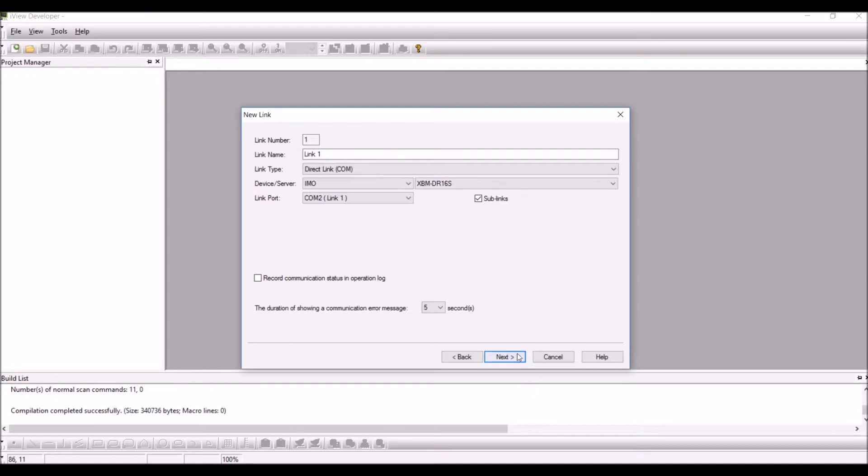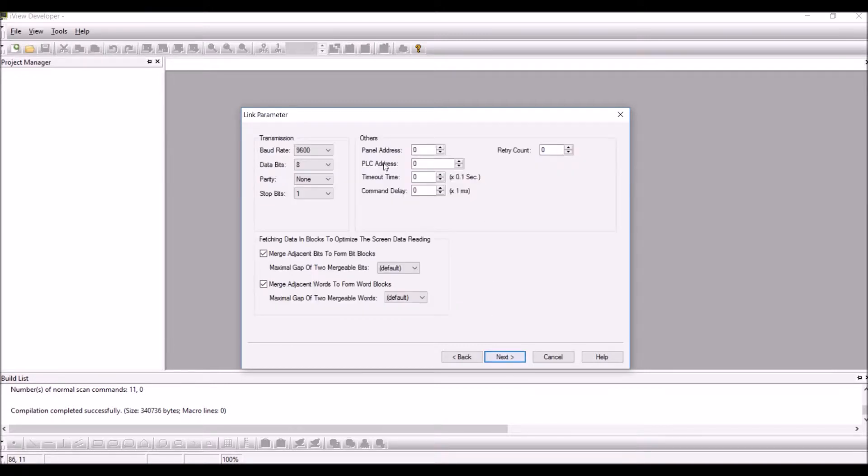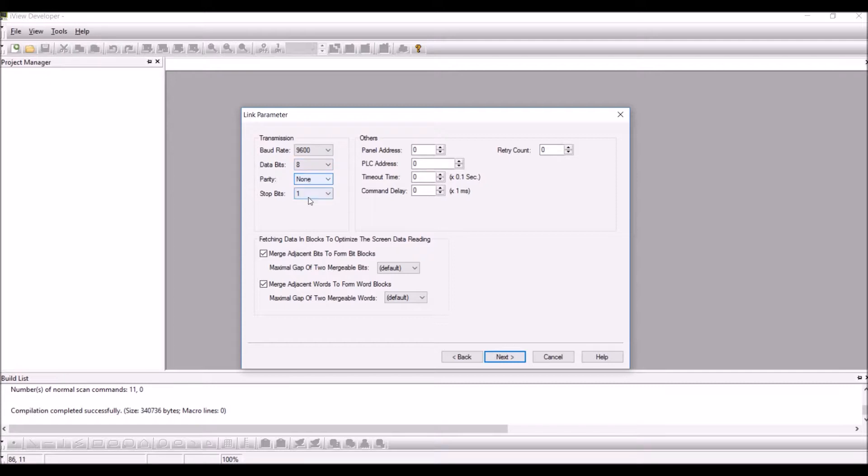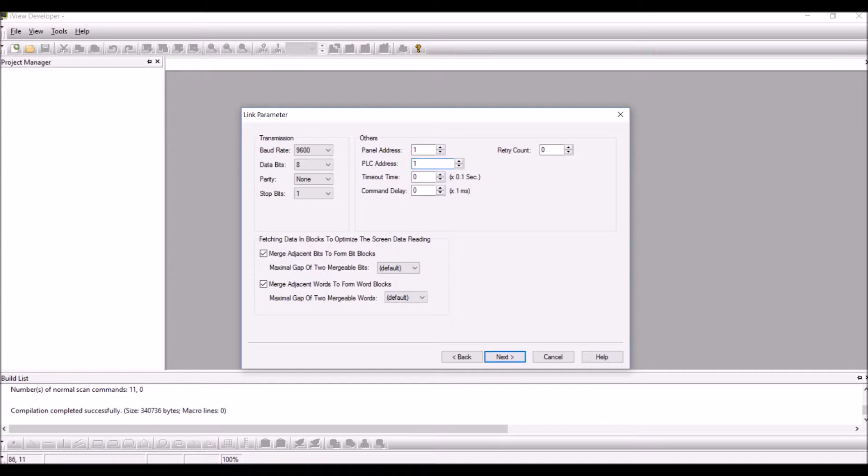Click on next, select the baud rate and all the other network parameters. Here I have selected 9600 baud, 8 data bits, no parity, and one stop bit. Select the panel address as 1, PLC address as 1, timeout as 10, and retry count as 3, and click on next.